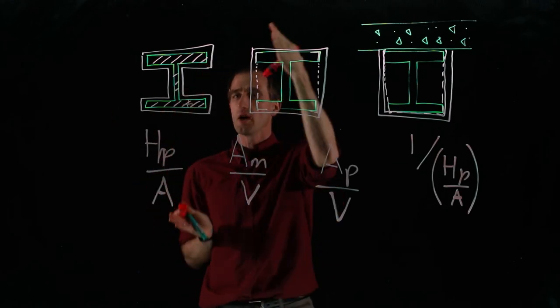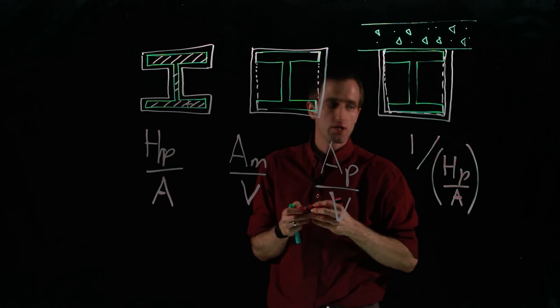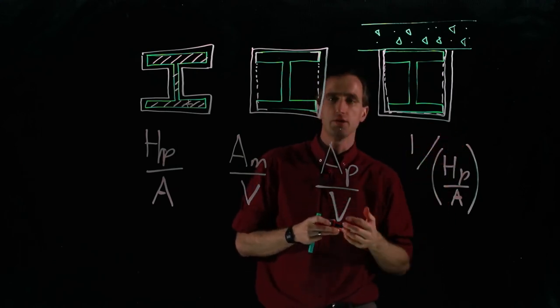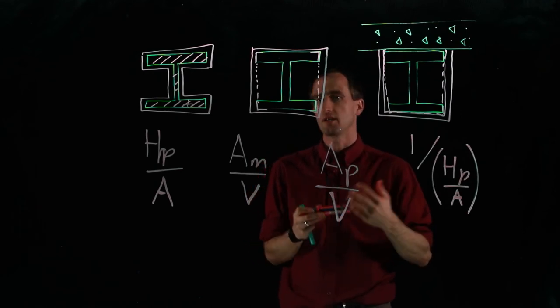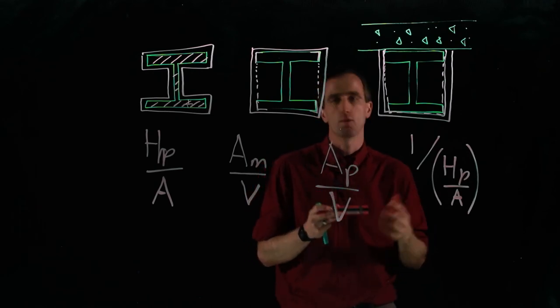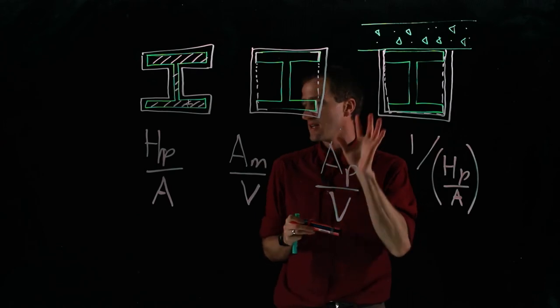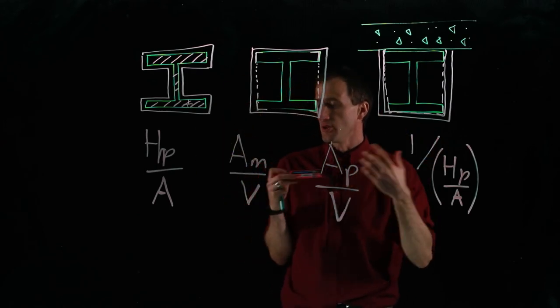On average, it's the same as saying this is a 10 millimeter thick plate with fire from both sides. So it's often not a bad thing just to double check your calcs by using that. You can use the effective thickness to see a sort of practical, conceptual way of visualizing what you've just calculated.